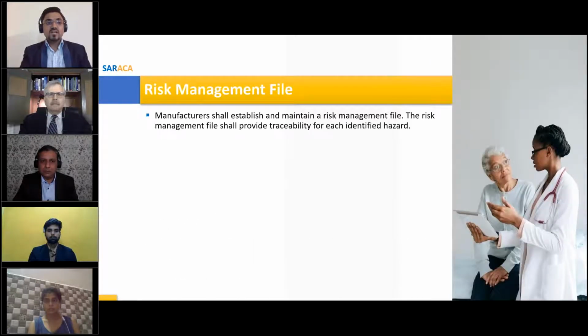Risk management file. The risk management file is the file which contains all types of risk documentation of your medical device. The manufacturer shall establish and maintain this risk management file, because the RMF is most required in the portion where you need to trace your hazards.